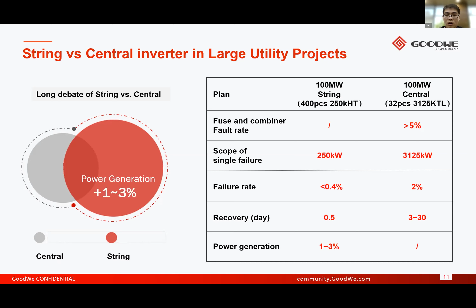Objectively, both string and central have pros and cons. String has a multiple MPPT feature to reduce the impact on your production due to shading or defects of your PV module. Another factor string inverters solve is mismatch loss when PV modules degrade. And although it's a very marginal difference of 0.6 to 0.8 as the years increase between year 1 and 25, as you can understand, the degradation of modules increases. So the defects increase and will reduce the expectancy of your plant. So the string inverter allows the maximum production for any degradation that is potentially happening.